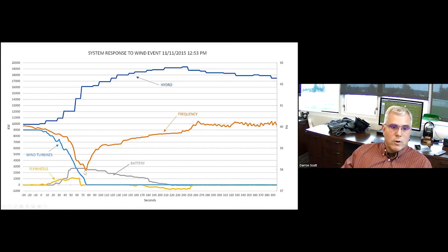And then the batteries are giving all they can. We've retuned the flywheels a little bit, because the negative with flywheels—the positive is you can hit them all day long, 2,000 times a day—the negative is they have a very short life of energy output. Ours run at 1 megawatt for 16.5 seconds. That's all you get out of them at full load.